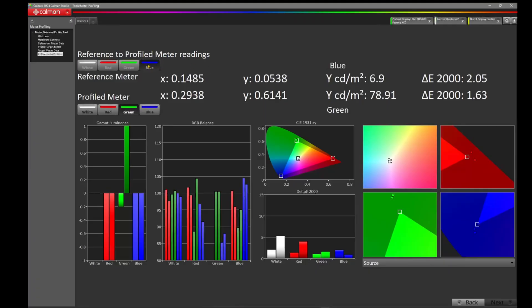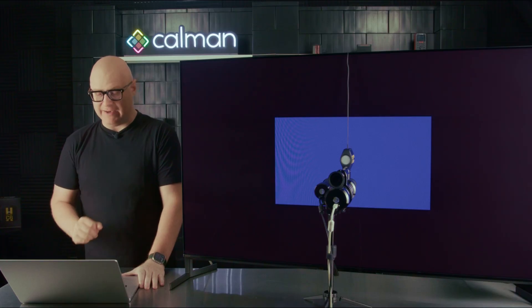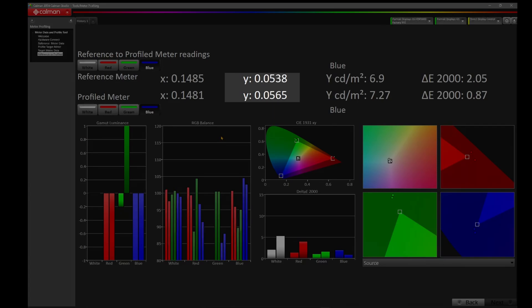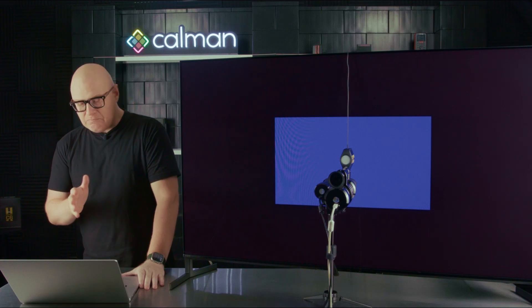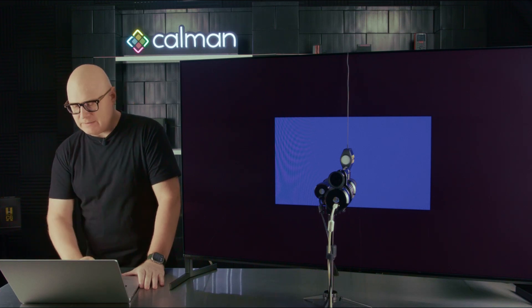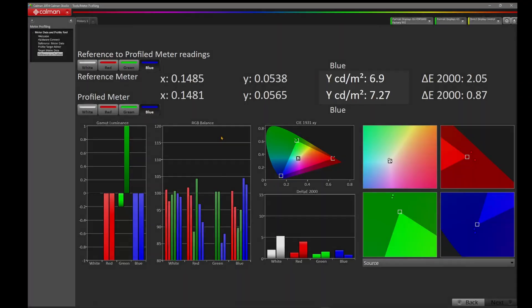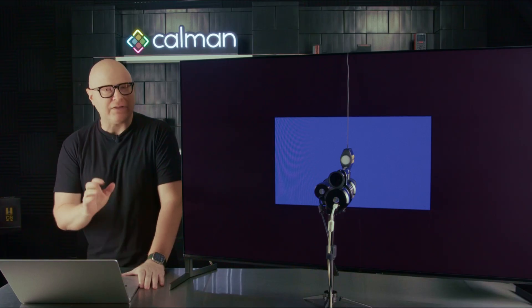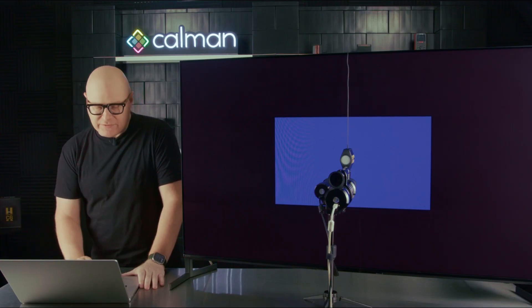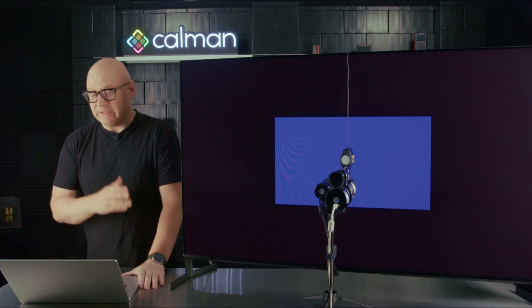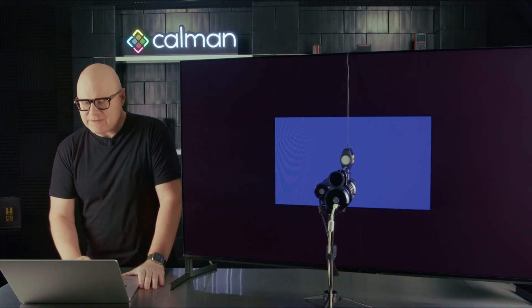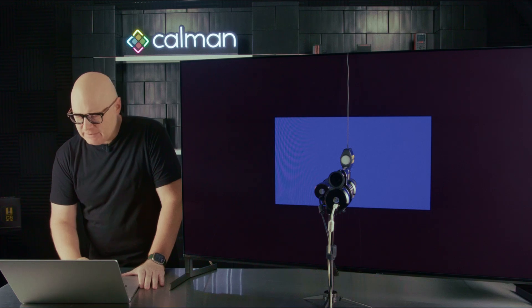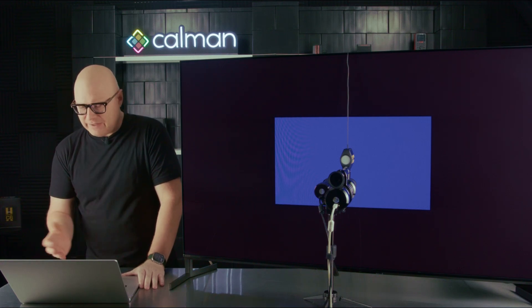Let's move over to blue. 0.1485, 0.1481. Not too bad. Y, 0.0538, 0.0565. Borderline for us. And then blue Y, 6.9, 7.27. Not too terrible there, but there were a couple, as you could see with the red, with the green, and even the white, where we had some errors that might not be acceptable.